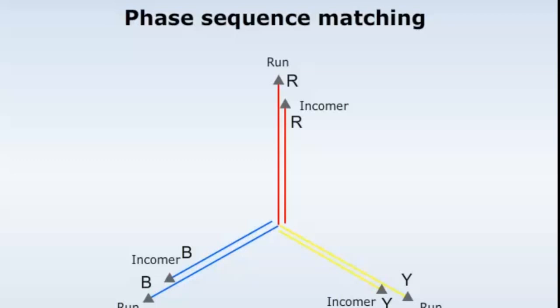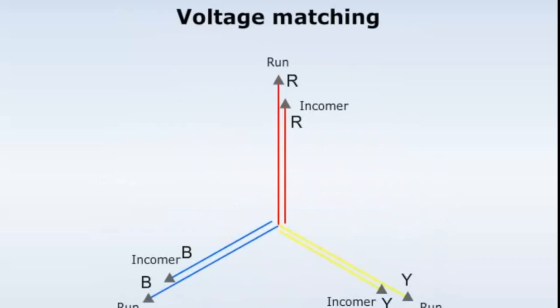The first condition is that the phase sequence of the incoming alternator should match the phase sequence of the running alternator. For example, if the phase sequence of the incoming alternator is RYB, then the phase sequence of the running alternator must also be RYB. At this condition, both alternators are rotating in the same direction with the same phase sequence. If the phase sequences are not the same, they are rotating in opposite directions.